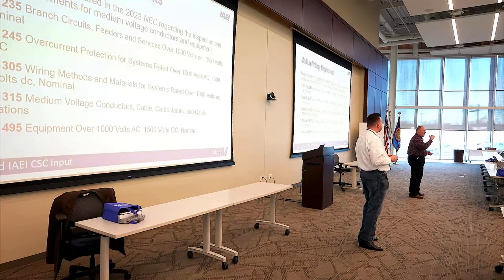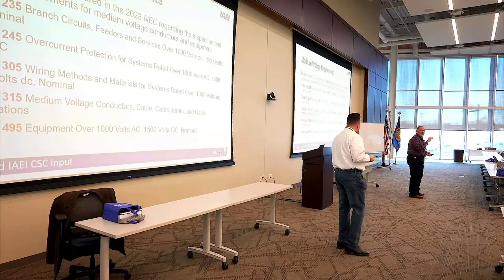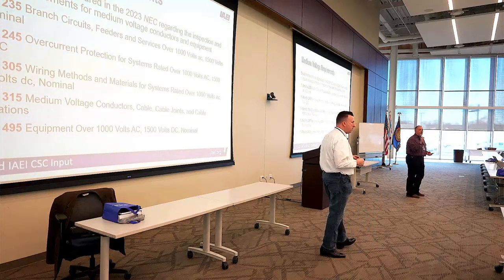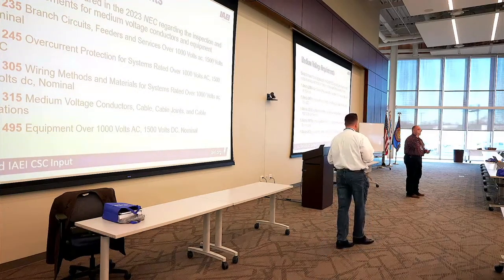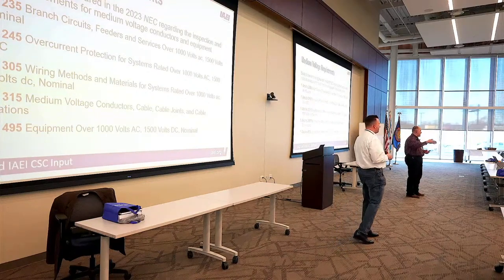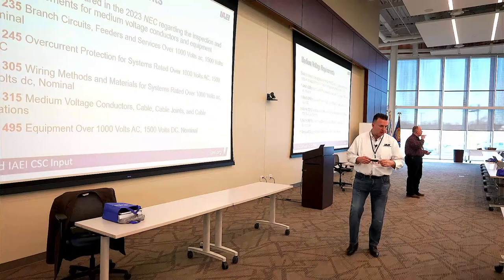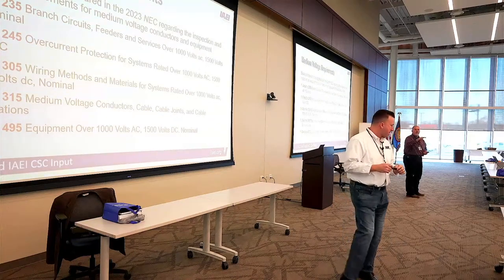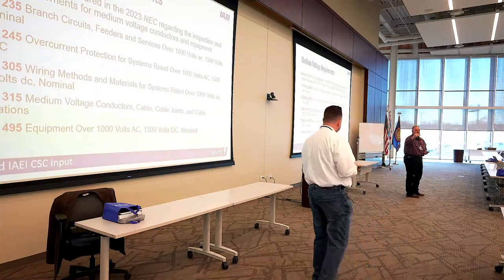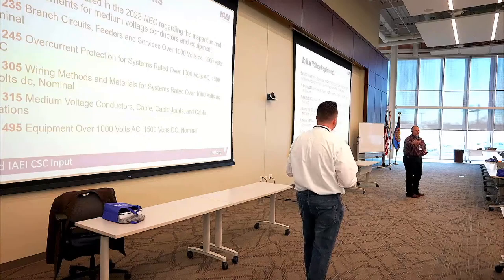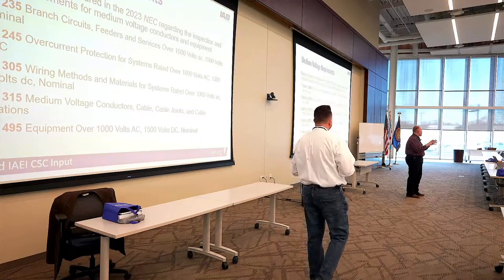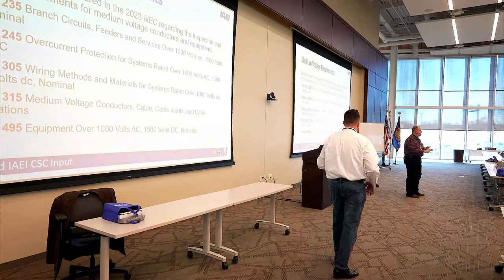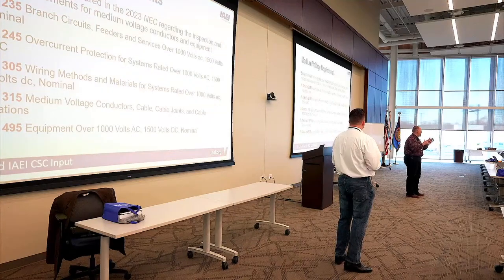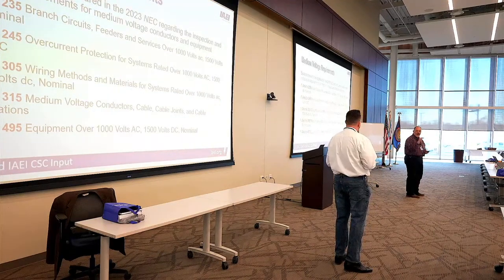So we increased the AC up to 1,000. The DC is 1,500. The reason is to align with international and IEEE standards. Internationally, 1,500 is recognized as your line of demarcation for medium voltage when it comes to DC applications. And in all of your IEEE, Institute of Electrical and Electronic Engineers, technical references, they all recognize 1,500 volts DC as that line of demarcation.